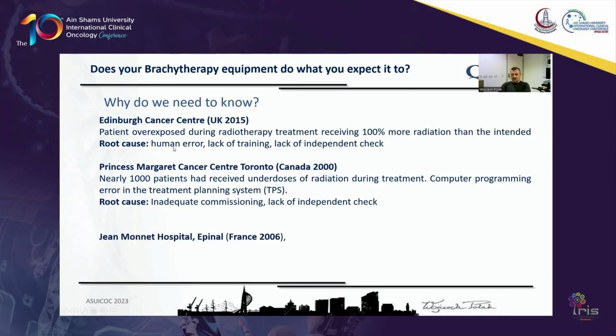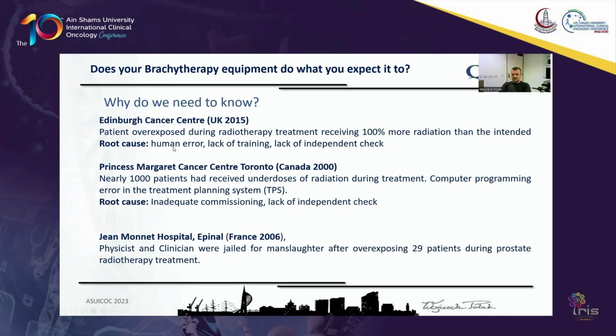Another one in France in 2006, where physicists and clinicians were jailed for manslaughter after overexposing 29 patients during the prostate radiotherapy treatment. And again, the root cause was human error, incorrect commissioning of treatment planning software, lack of independent check and audit, and in this case, also trying to cover up the error instead of actually admitting that something like that happened.